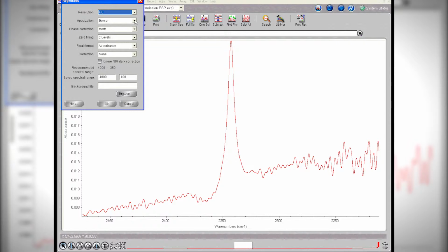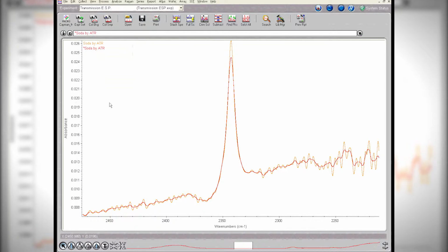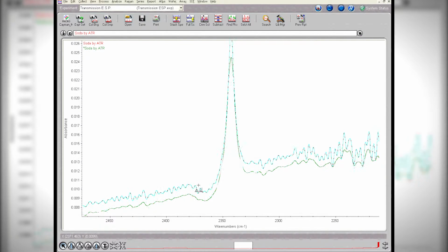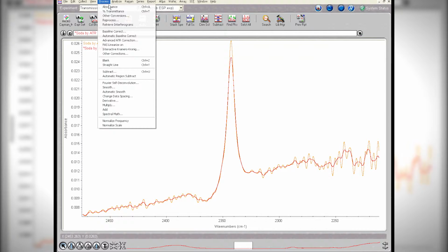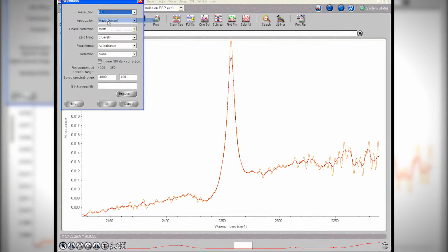Now this is what's called boxcar, so it has no apodization. Now I'm going to apply a moderate apodization to it, what's called a Happ-Genzel. You can see immediately the effect of apodization. It removes this noise, this Fourier transform noise you see all through here, is largely damped out when I apply that particular apodization.